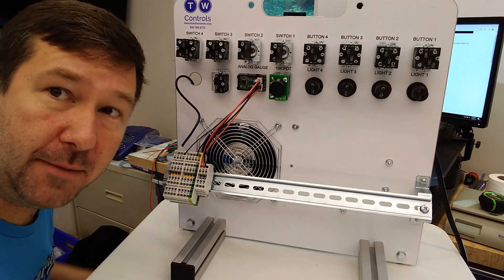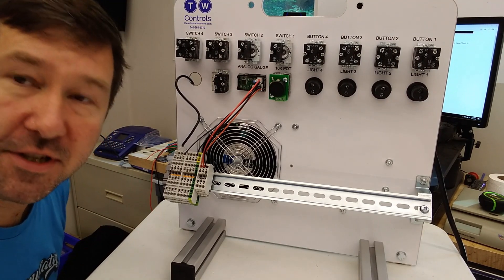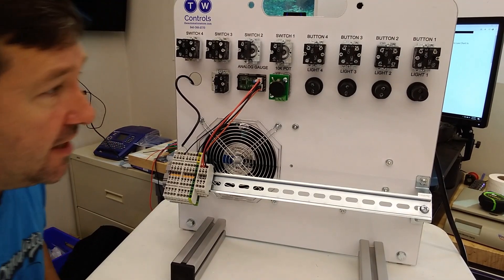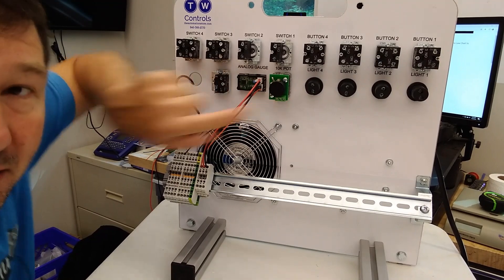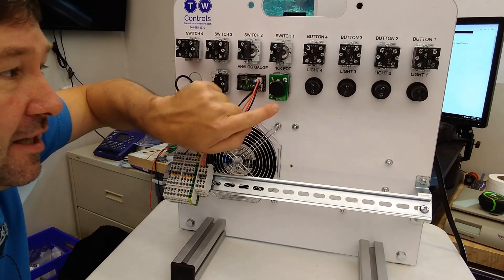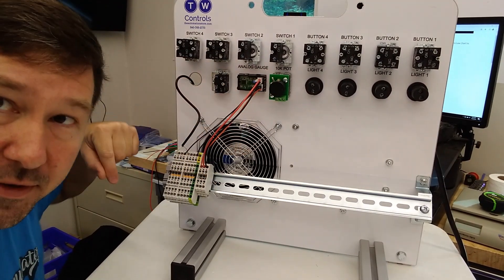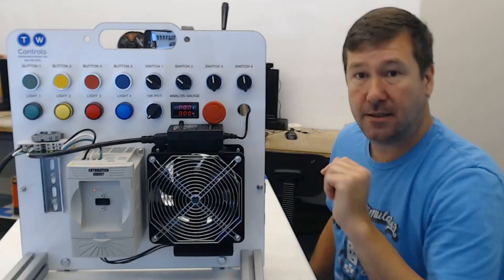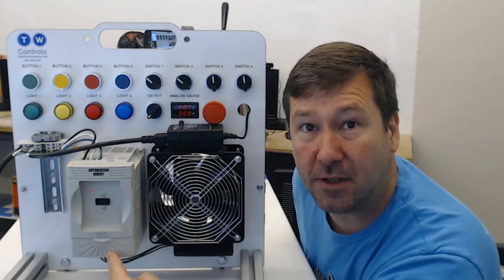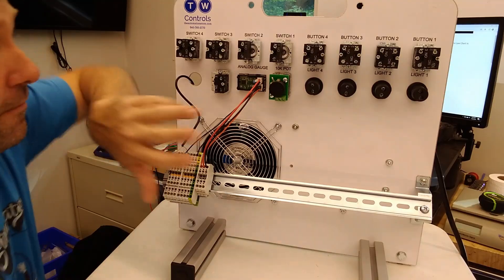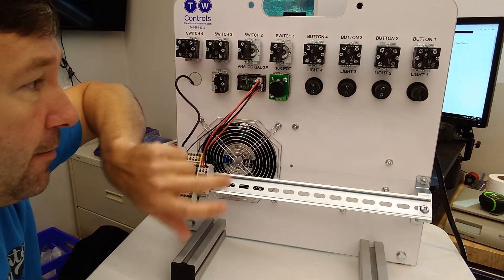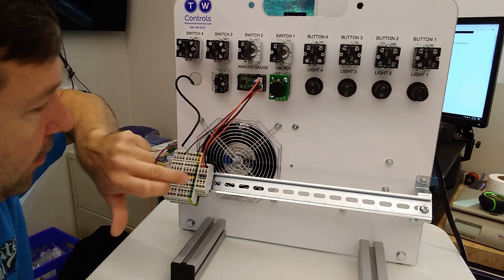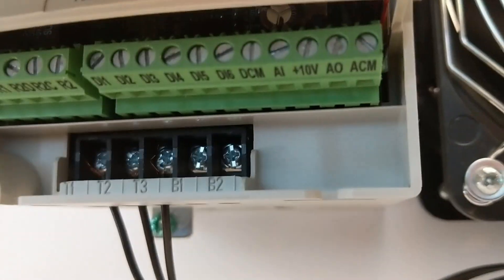Now typically a potentiometer connected to a drive or something like that, it'll be 10 volt between your two outside terminals and then your analog signal will come off at the middle terminal. So what I'm going to do is I'm going to get 10 volt off of our drive over here and wire it into our potentiometer, and then I will take the middle signal and wire it to our display.